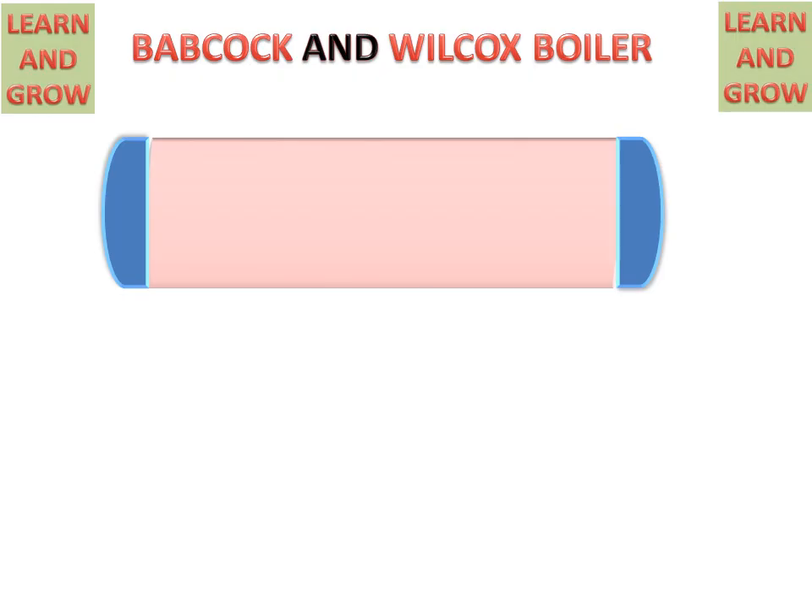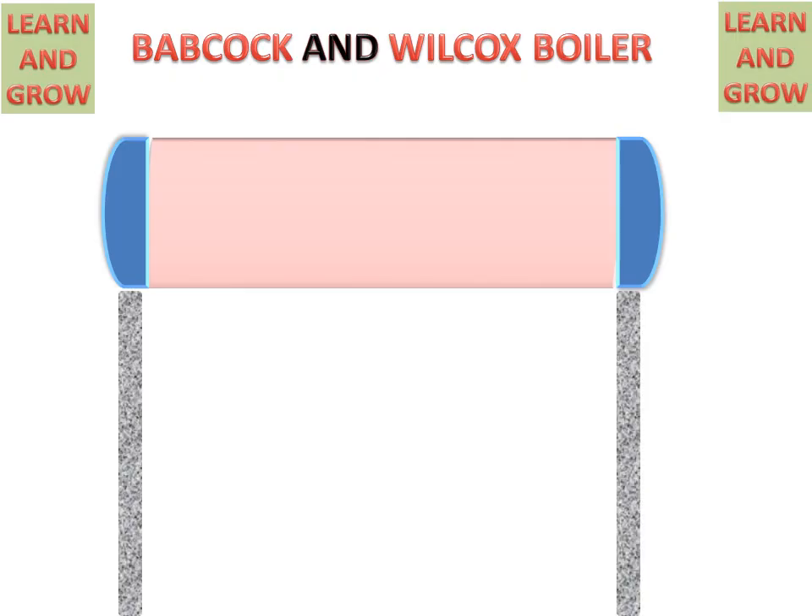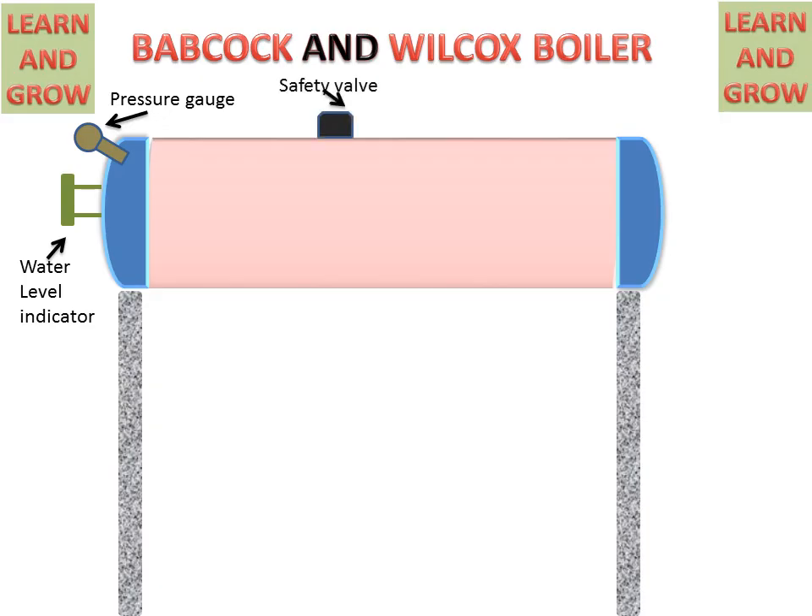We have a welded steel high pressure drum mounted at the top. These are the supports for the shell. There is a water level indicator on the left hand side as we see in the figure. It is used for seeing the water level in the steam and water drum. This is the pressure gauge for noting down pressure in the steam and water drum. This is the safety valve for safe working of the boiler. This is the manhole for cleaning purposes of the boiler at maintenance time.